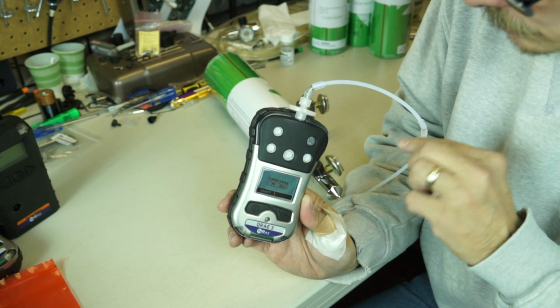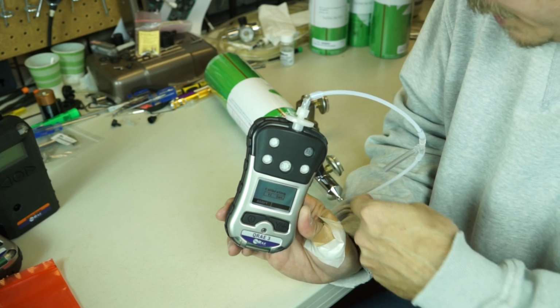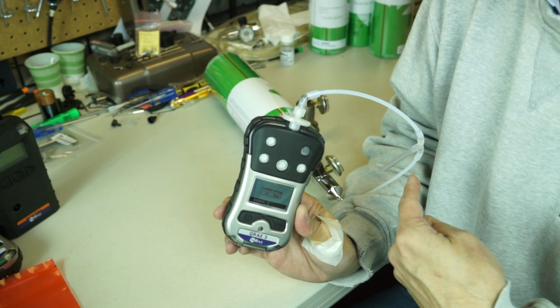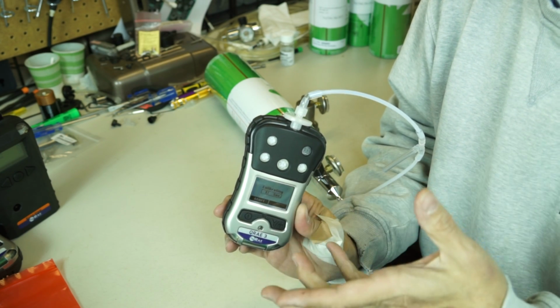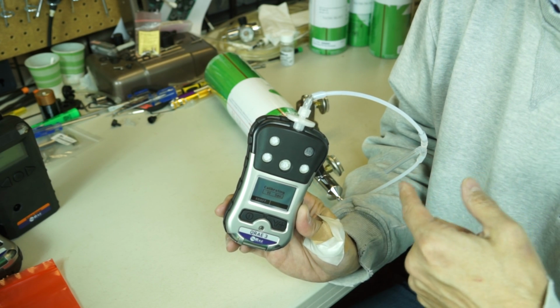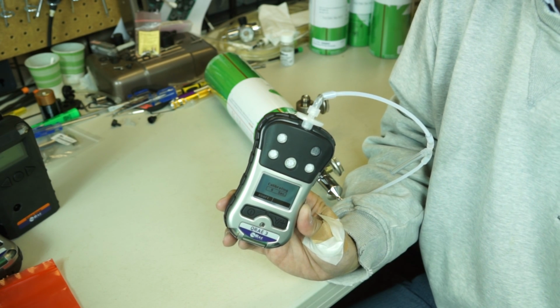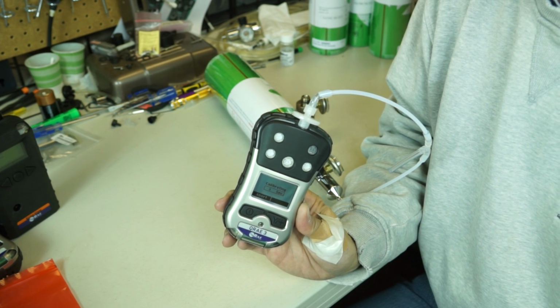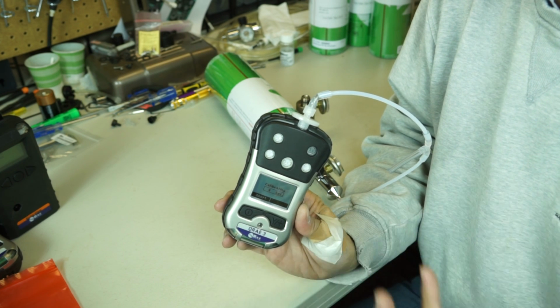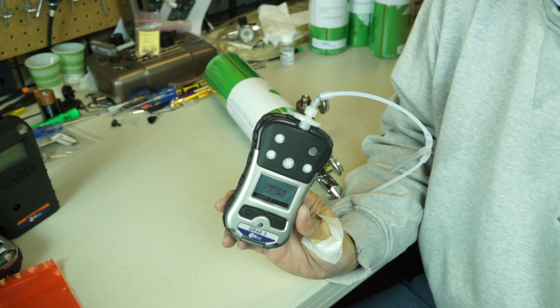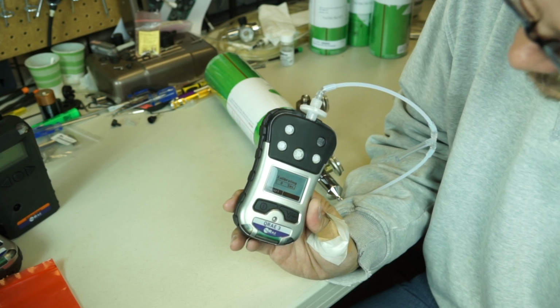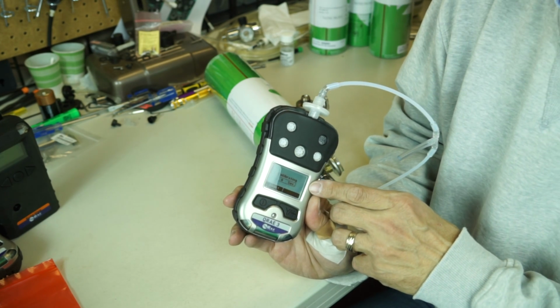What you wouldn't want to do is just use tubing and force the gas in without a T. A pump that doesn't pull will actually be calibrated by forcing the gas through the system. And then when you go out into the field to use it, it would then cease to work because it's not pulling anything in, and it would be zero all the time. That's very, very dangerous. It's calibrating. It's down to 0.